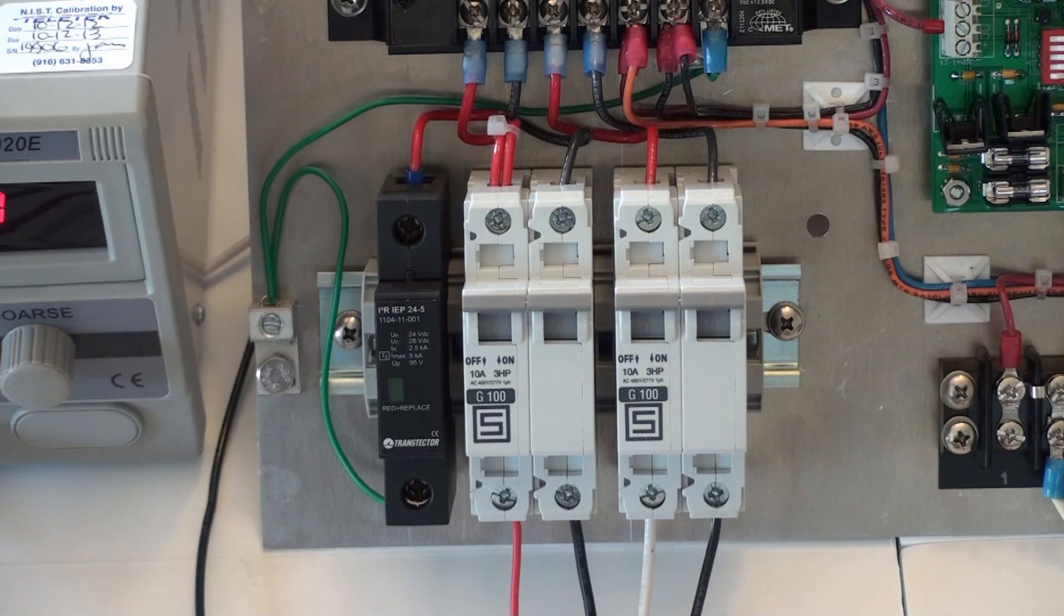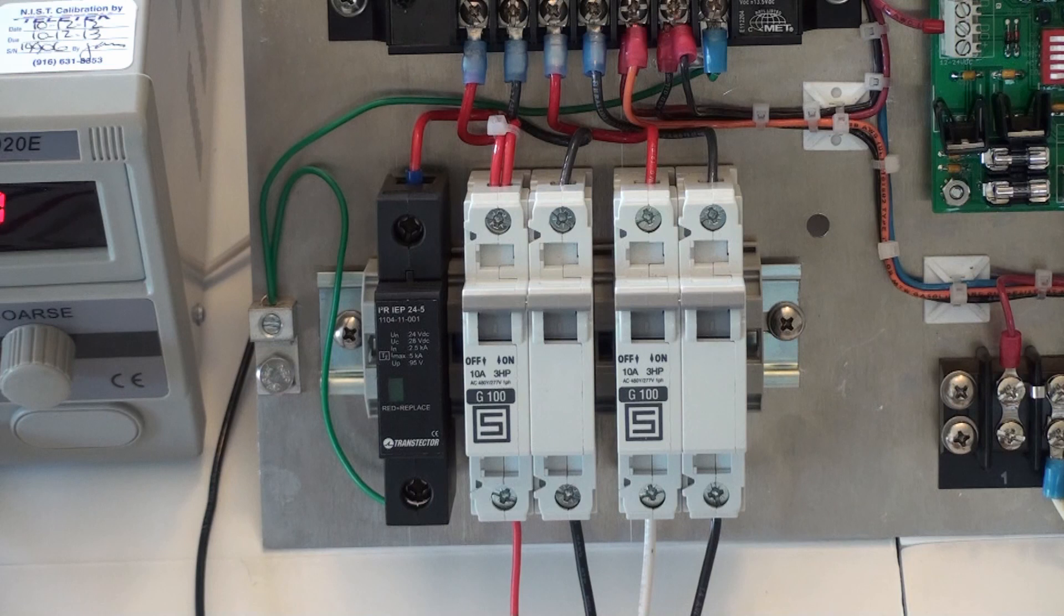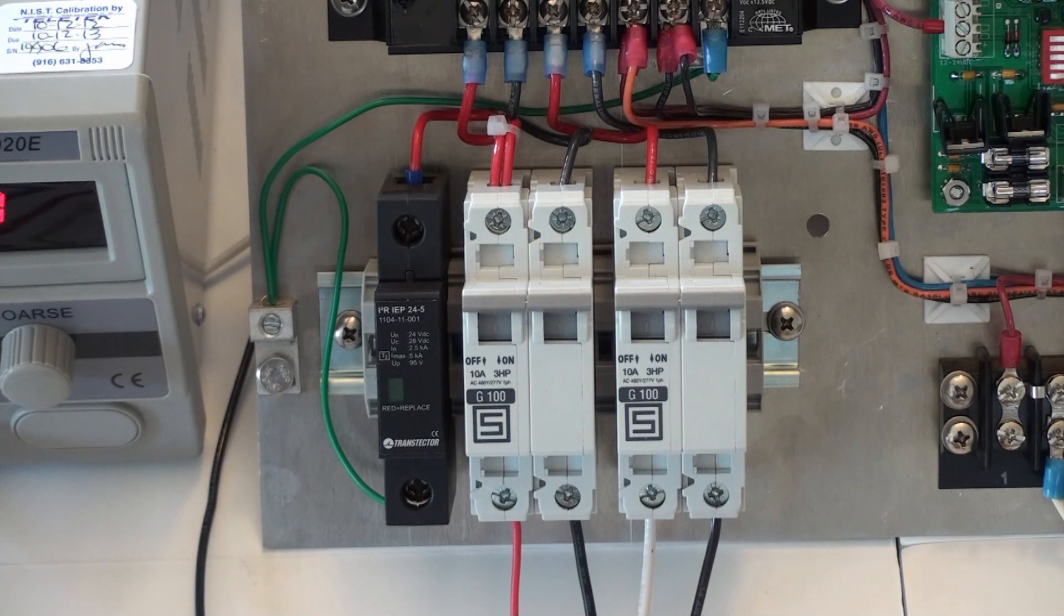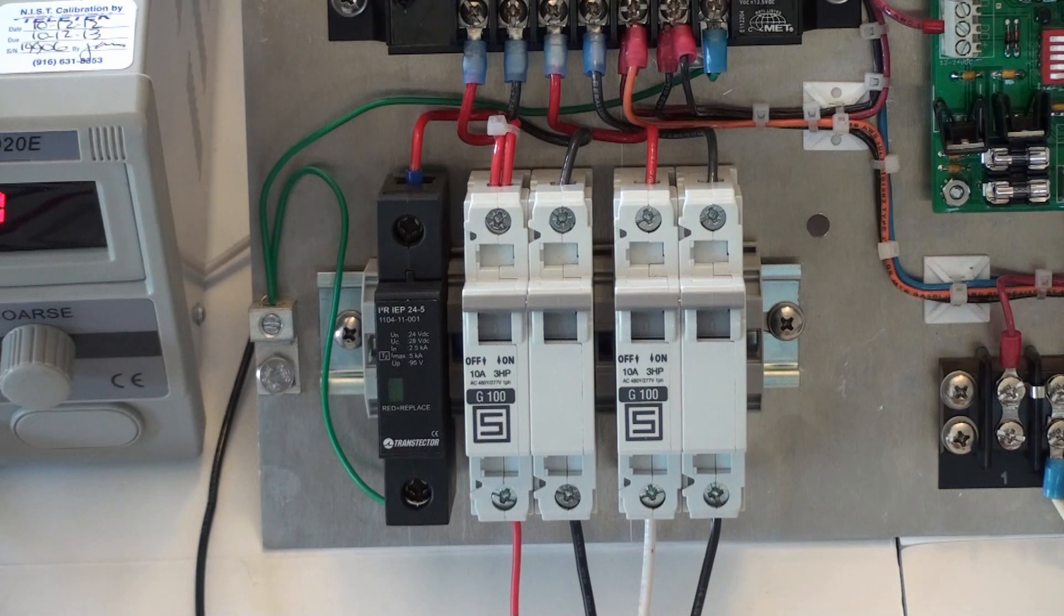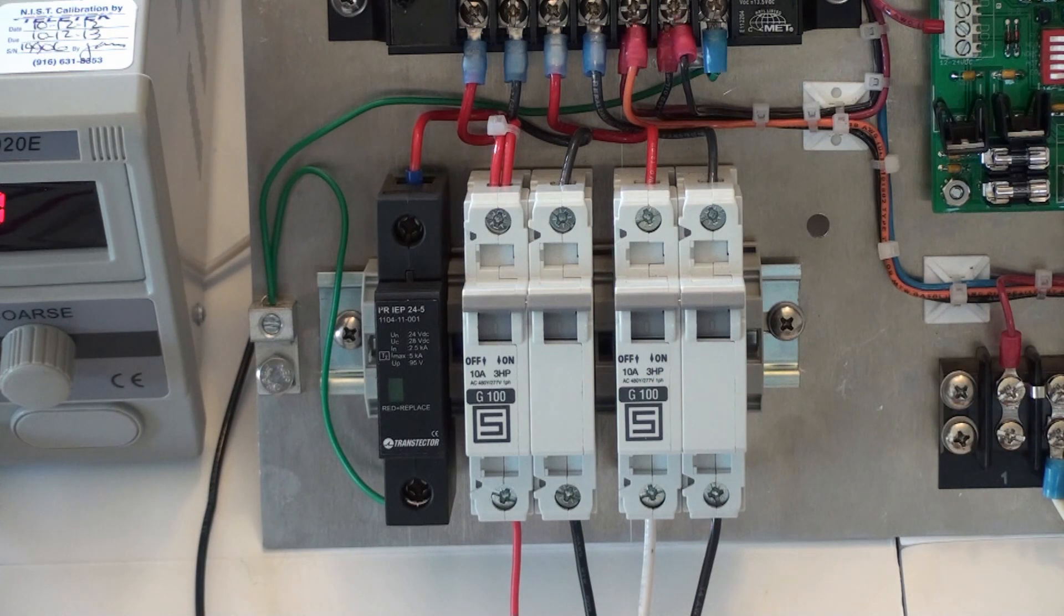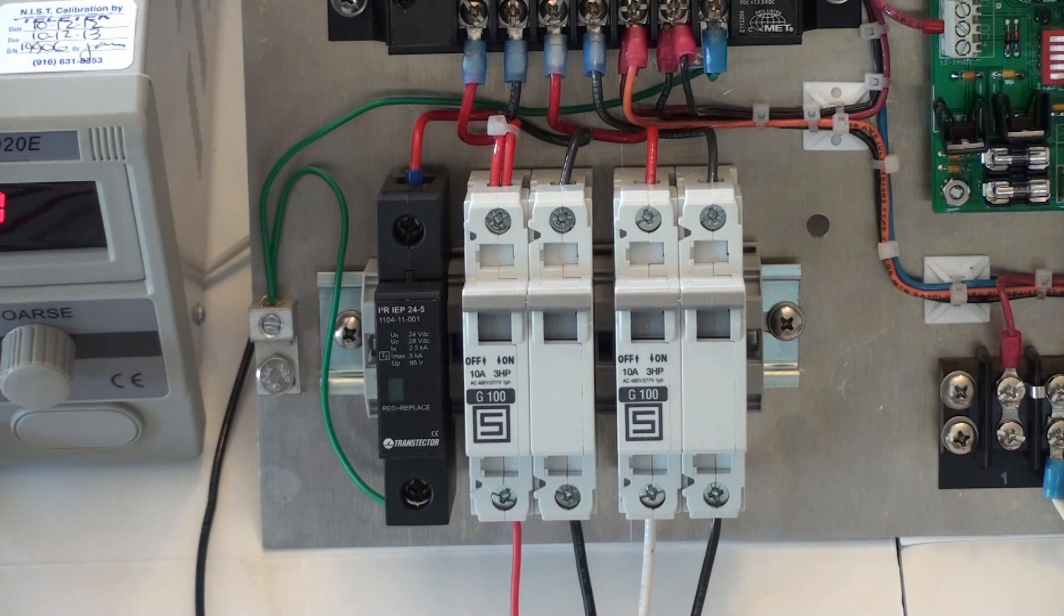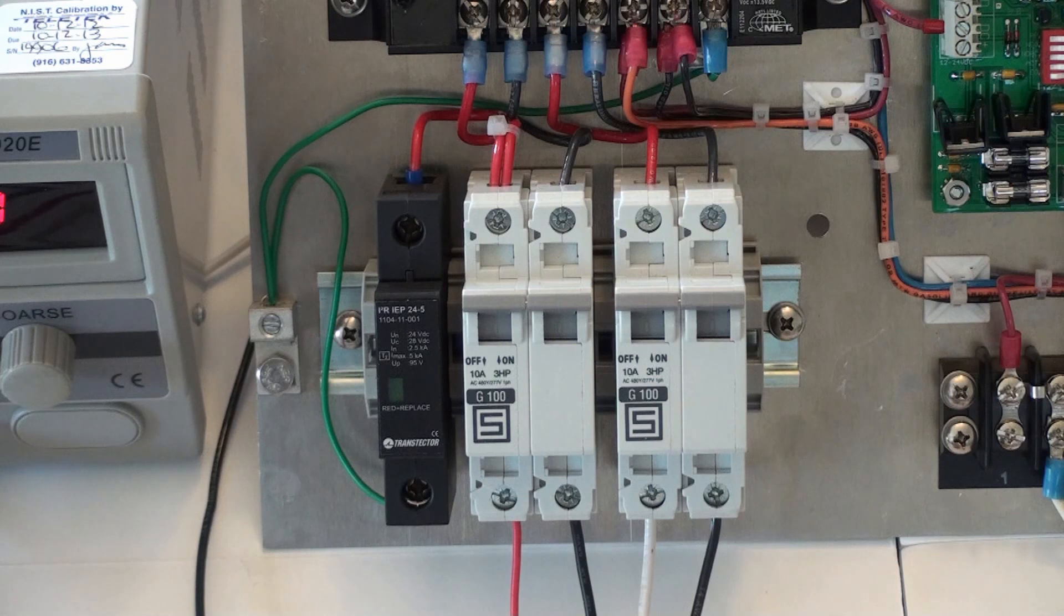If the window is red, it indicates that the surge protection device has been damaged by a high voltage transient, which is most likely caused as a result of a nearby lightning strike.